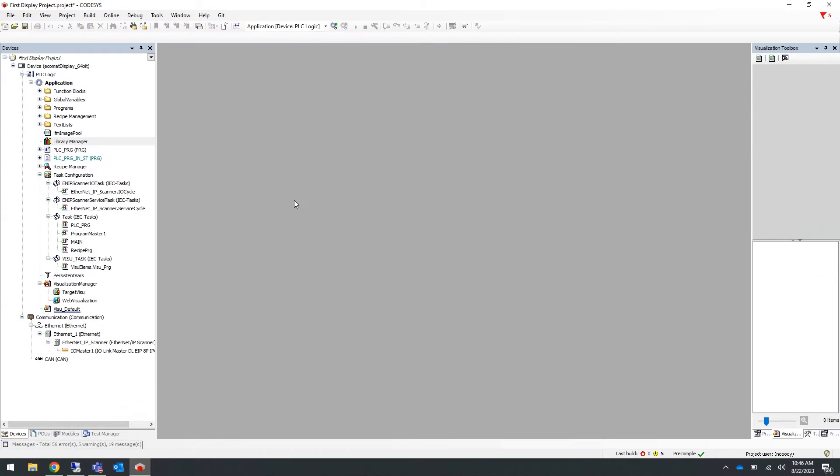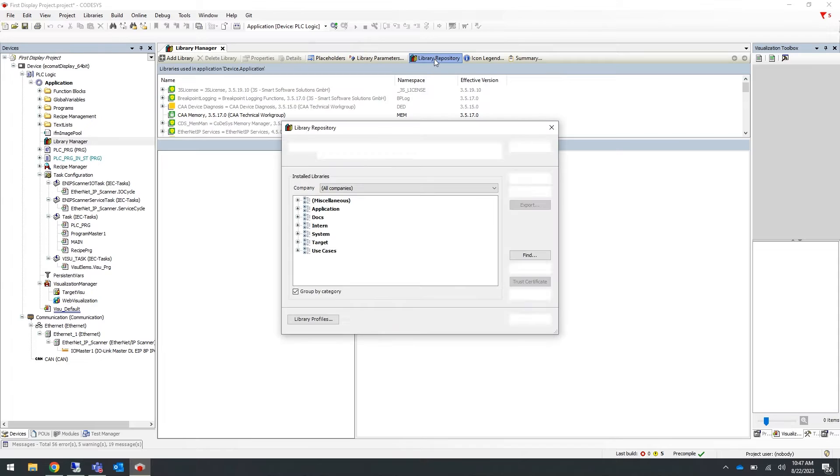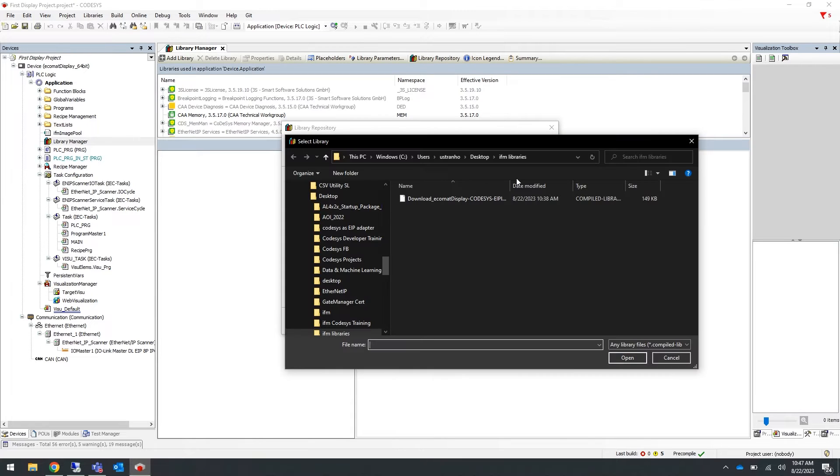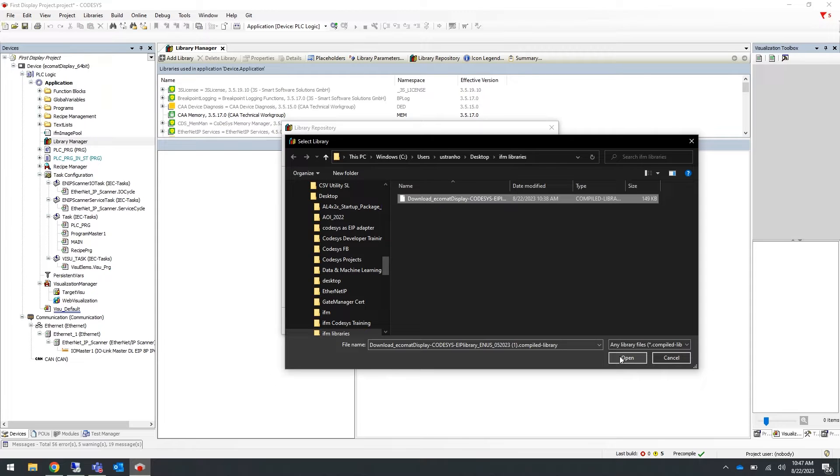Now to install the IFM EIP library in the CODESYS programming software, select the library manager on the left-hand side. Within the library manager, select library repository and then select install. Navigate to the library that you just downloaded from the IFM website and select it and click open. For the purposes of this video, we have already installed this library so we will skip this step now.